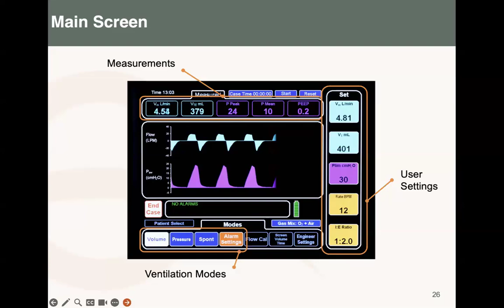Like the oxygen sensor, this also needs to be calibrated. You disconnect the drive hose, you connect the red adapter, and you orient the flow sensor as it's shown. You go for the calibration, where you select calibrate the flow sensor. Once it's done, it will tell you to reverse, and once it's complete, it will display.